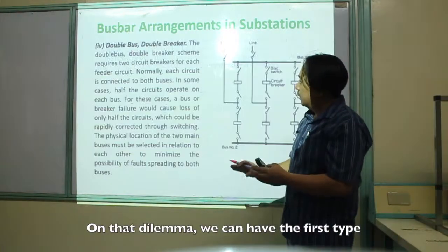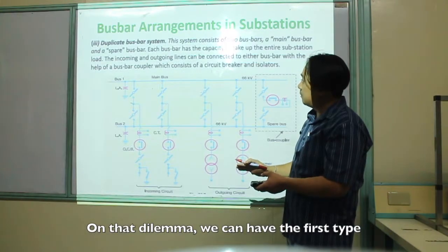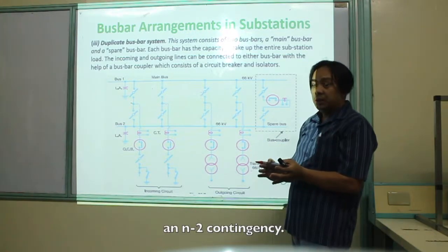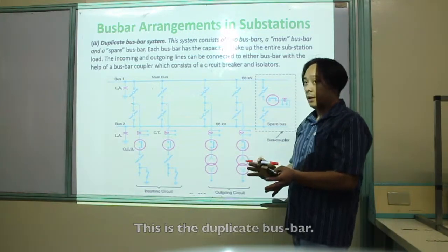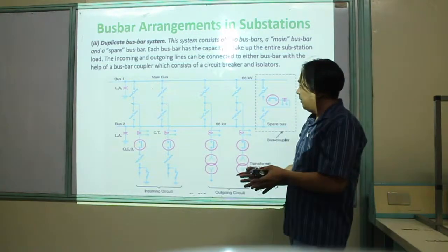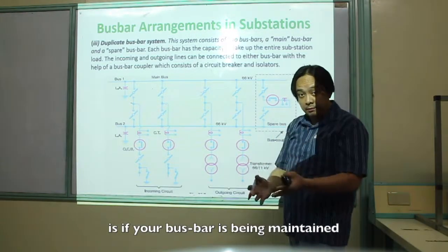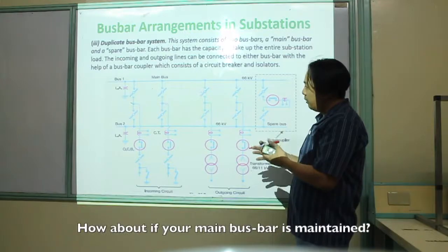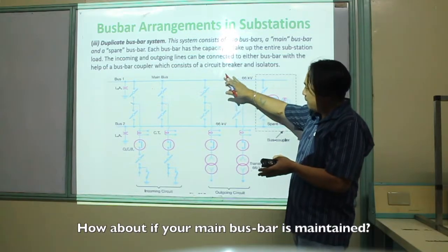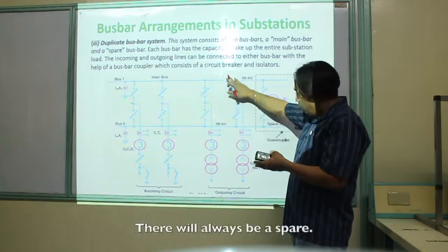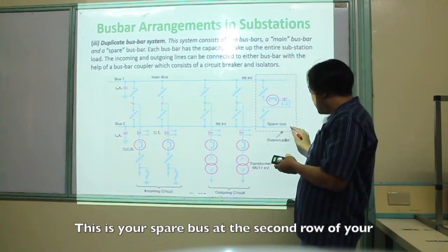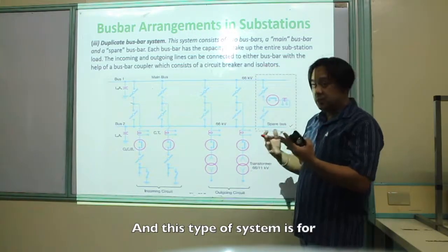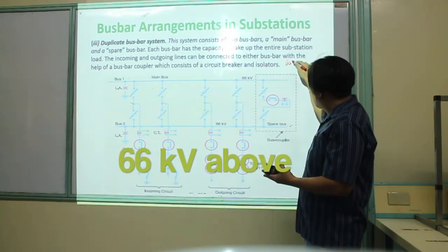For N-2 contingency, we have the duplicate bus bar. The problem with the first two types is that if your bus bar is faulted or being maintained, there is a complete interruption. With the duplicate bus bar, if your main bus bar is being maintained, there is always a spare — a spare bus at the second row of your power system. This type of system is for 66 kV and above.